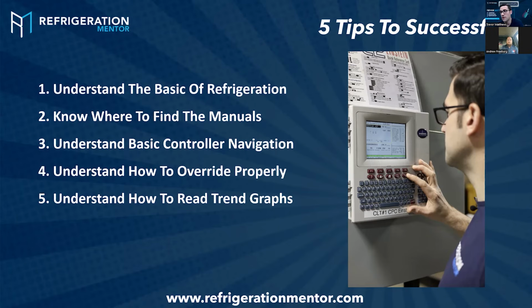Last one, and you already talked about it, to be successful I think the biggest and number one is reading trend graphs. If you can read trend graphs properly, you can troubleshoot a system from anywhere, as long as it has the proper data to read. And now with CO2 systems, we know there's temperature and pressure probes everywhere. What are a couple of tips for reading trend graphs, Andrew? My biggest tip is understanding what is good.